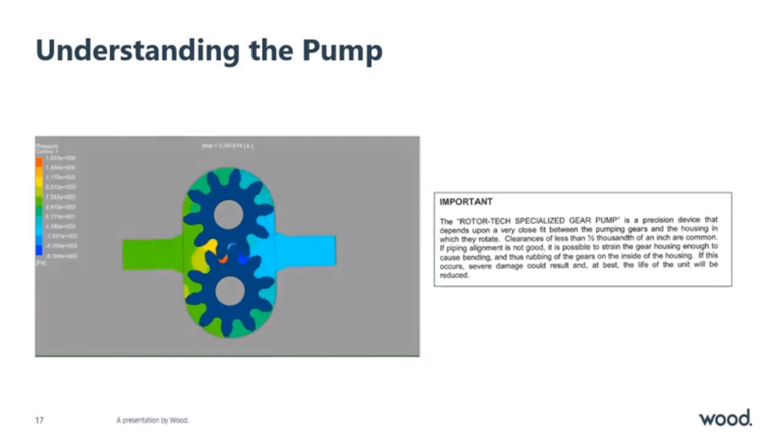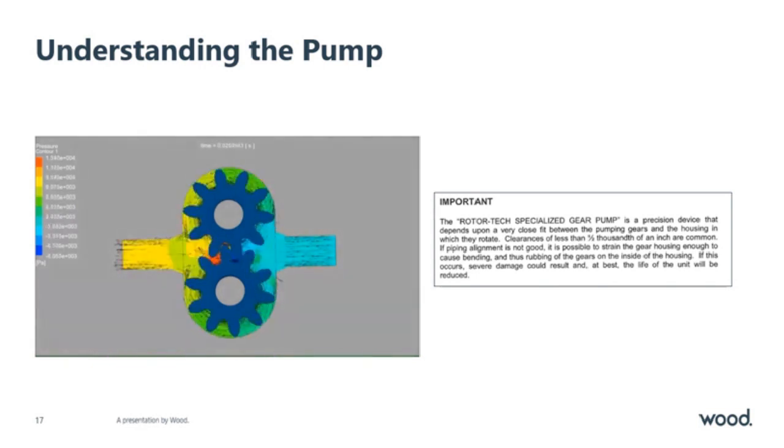So together with those scratches internally and the amount it was moving, you could see how wear would occur. And then, of course, you'd lose that efficiency. You'd start to get pump slippage and therefore the pump flow rate would drop.